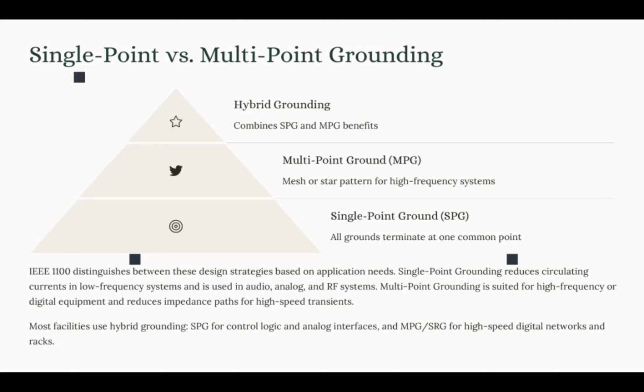It also improves the EMC, the electromagnetic compatibility, by reducing the radiated emission and susceptibility to external EMI, which it does by providing that low impedance return path that we talked about. Now, what is the limitation? It also has cost. And when we talk about multi-point grounding, you can imagine that there is a vulnerability to circulating current. We have some loops that at low frequency can create a problem of circulating current, which introduces noise into our analog sensitive equipment.